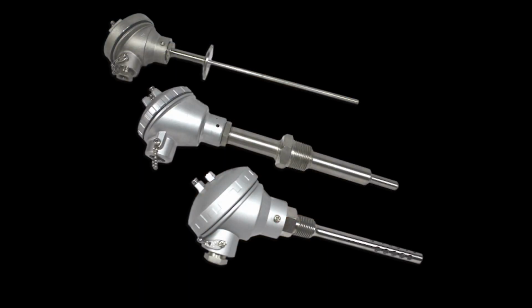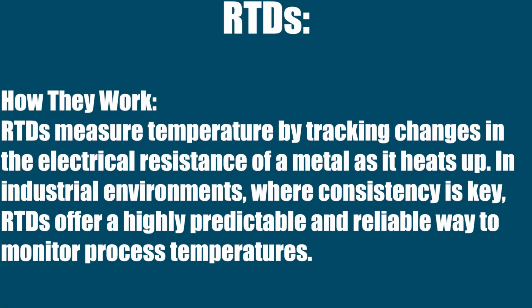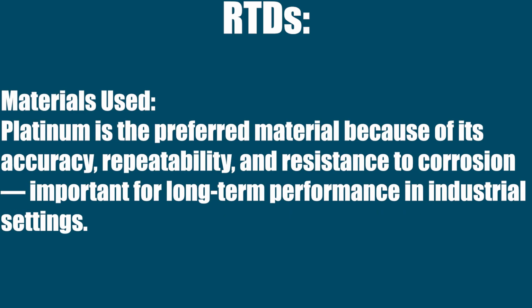First, we'll discuss RTDs, or resistance temperature detectors. Here's how they work. RTDs measure temperature by tracking changes in the electrical resistance of a metal as it heats up. In industrial environments where consistency is key, RTDs offer a highly predictable and reliable way to monitor process temperatures. The material used in an RTD is primarily platinum, a preferred material because of how accurate it is, its repeatability, and its resistance to corrosion. Very important for long-term performance in industrial settings.